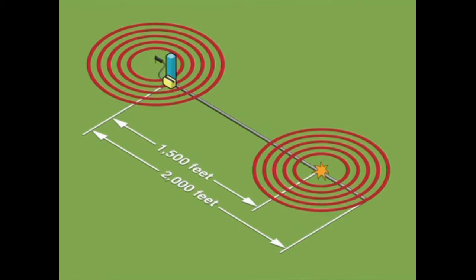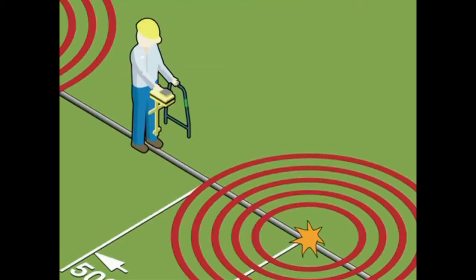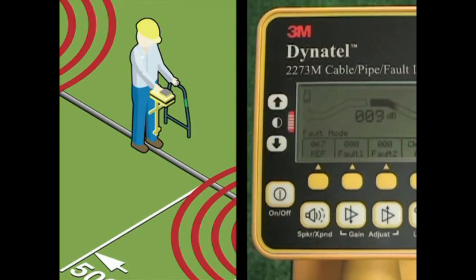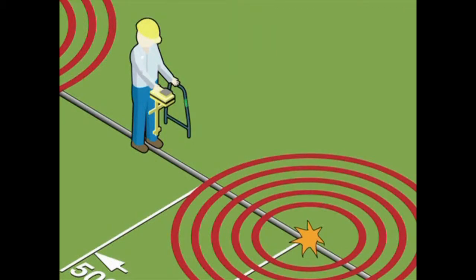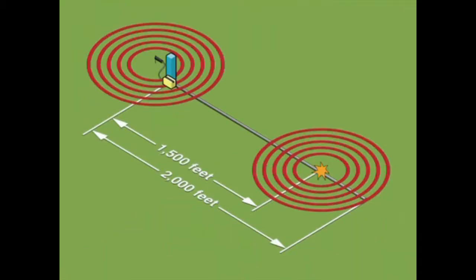But if your section of cable is 2,000 feet long, and the fault is at 1,500 feet, the fault signal pools or areas of detection may not overlap. If this is the case, you may find that the receiver will seem to be confused in the middle of the section or not give you a strong indication of red or green. It only means that you have walked out of one of the fault signal pools and have not yet entered the second. This poolless area is sometimes called a dead zone. For example, if you lose fault indications 500 feet away from the transmitter, you have entered the dead zone. This dead zone will continue until you are within 500 feet of the fault. Then you will begin detecting the fault again because you have entered the fault pool.